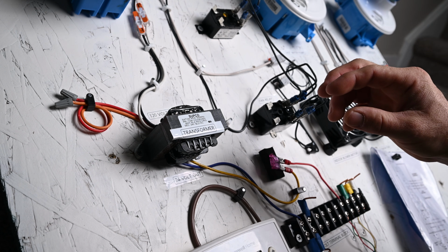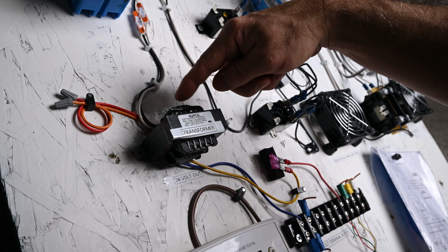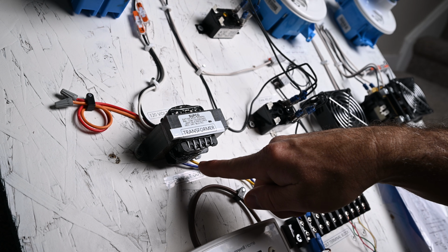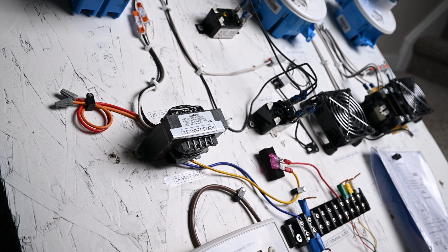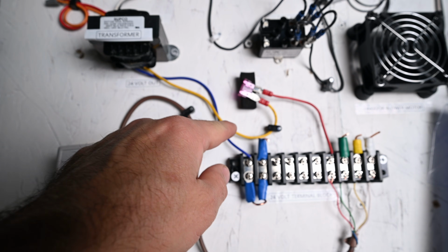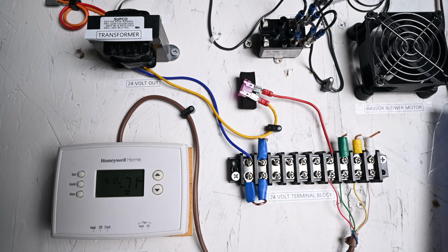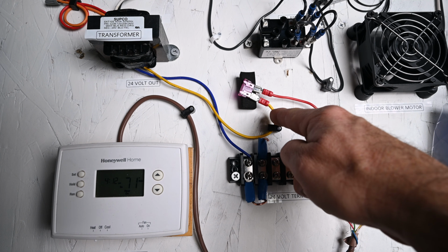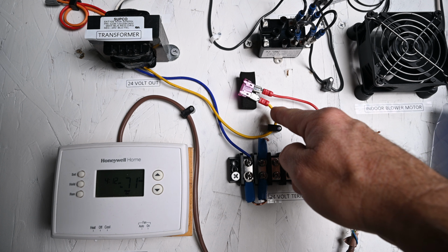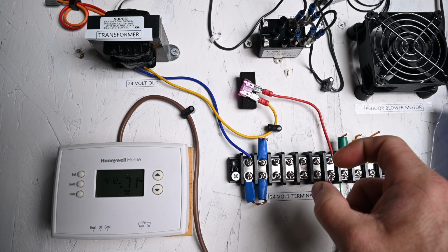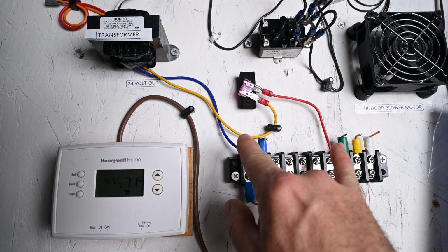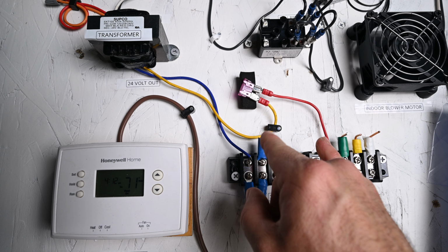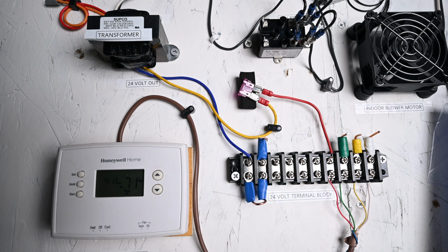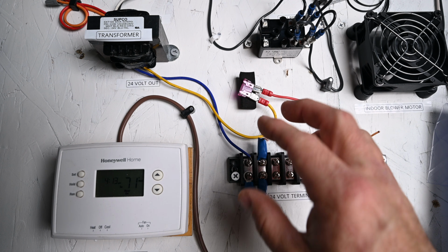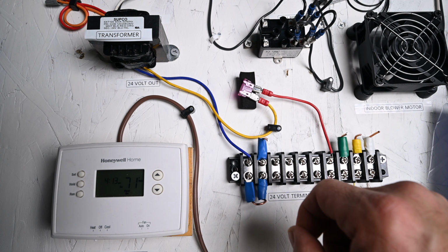Now, this is all real voltage. Our 120 volt right here is coming into the transformer. Exiting out of the transformer, it's stepping down the voltage to 24 volt. One of the wires, this blue wire, is our common wire. For any of these magnetic coils to energize, you need power, the 24 volt, and you need a common. When those two meet the coil, it'll energize the coil and pull in the plunger. If the common and the power wire touch at any point without a resistor in between them, such as a coil, then this fuse will pop or the transformer will short. This is why it's always very wise to fuse your transformers, or just get a transformer that's already fused.